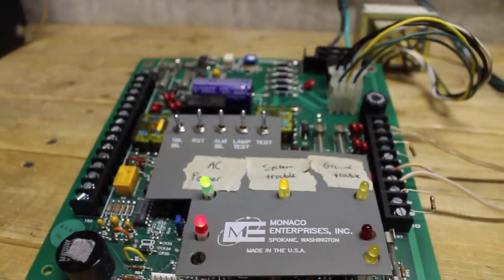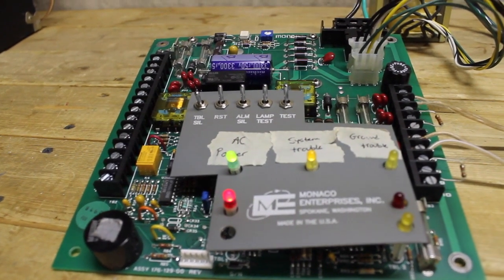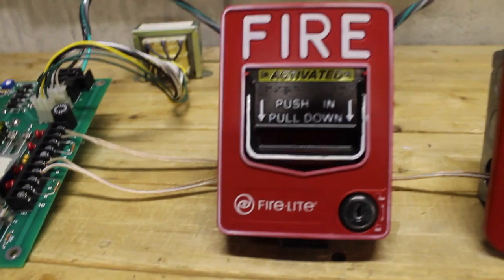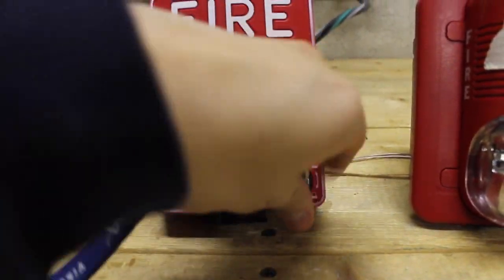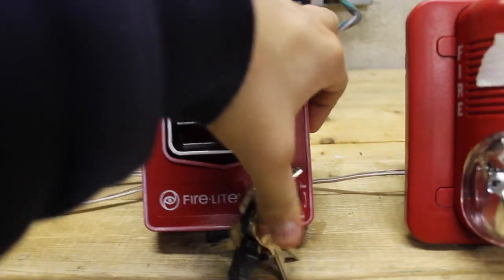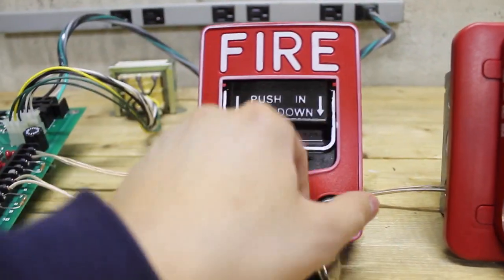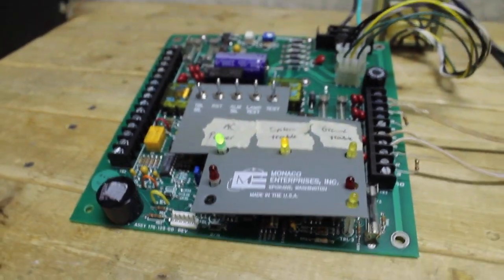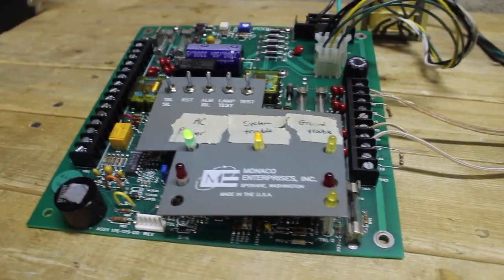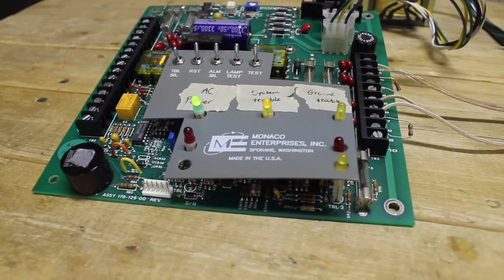Almost touched that big capacitor there — that would not be good. Now I cannot reset the panel just yet because I have not reset the pull station. Let me get my handy Fire-Lite key, stick that in there, and reset this. Now we can reset the panel. Otherwise, if I hadn't reset it, the circuit is still making contact — the switch is still closed — and it would just go back into alarm.